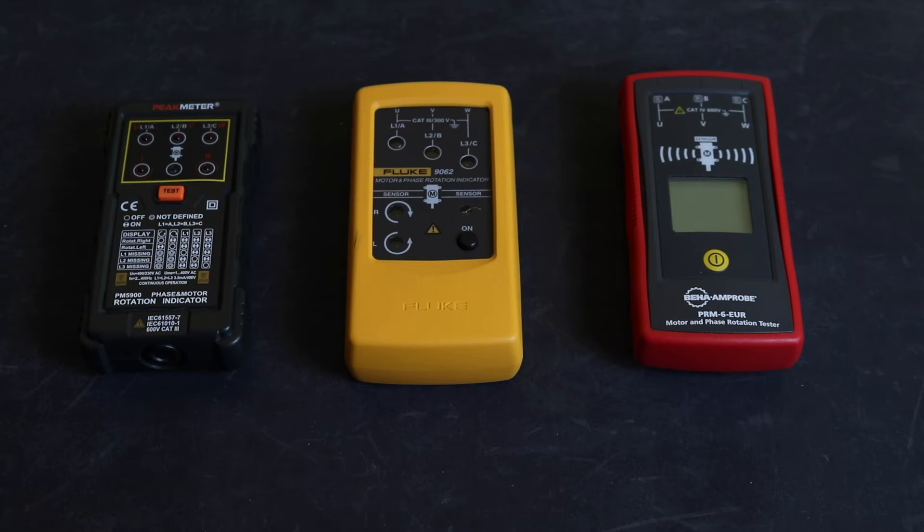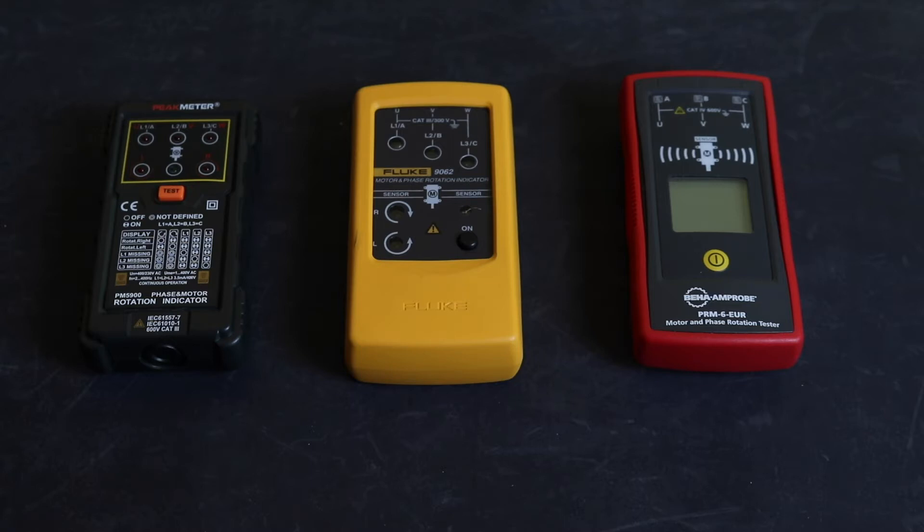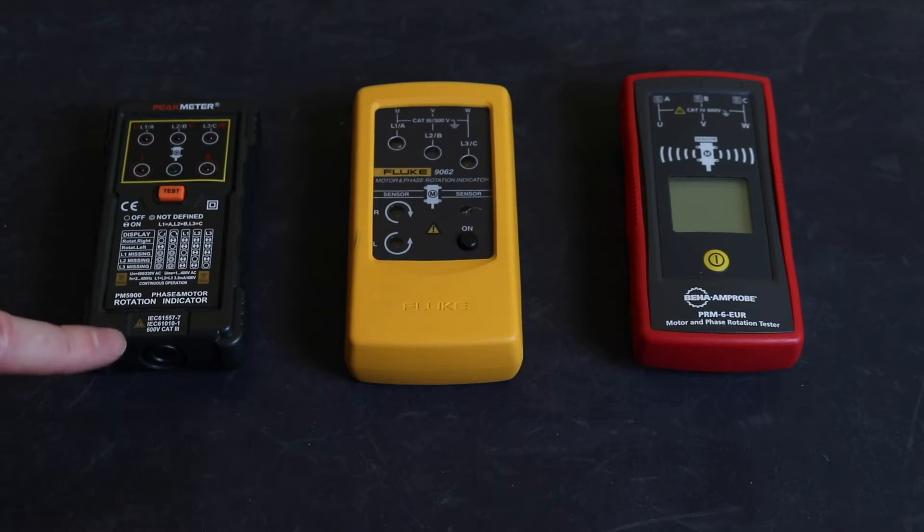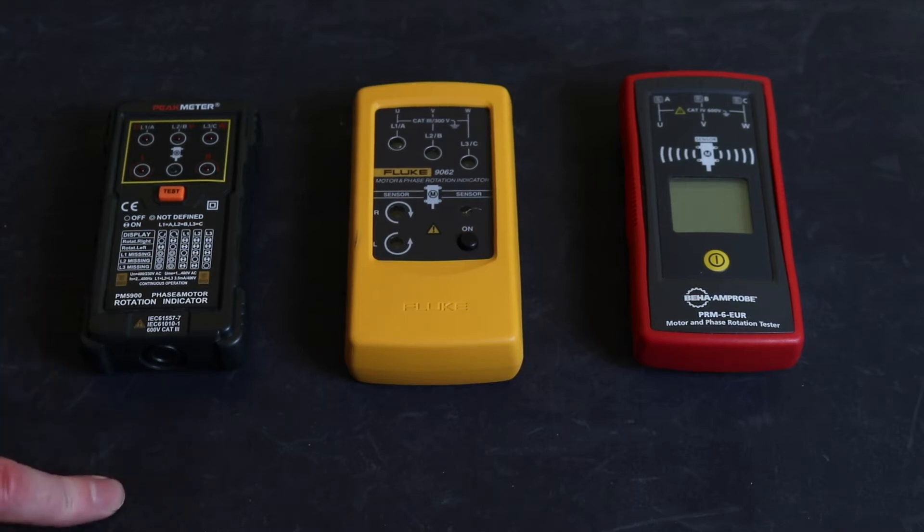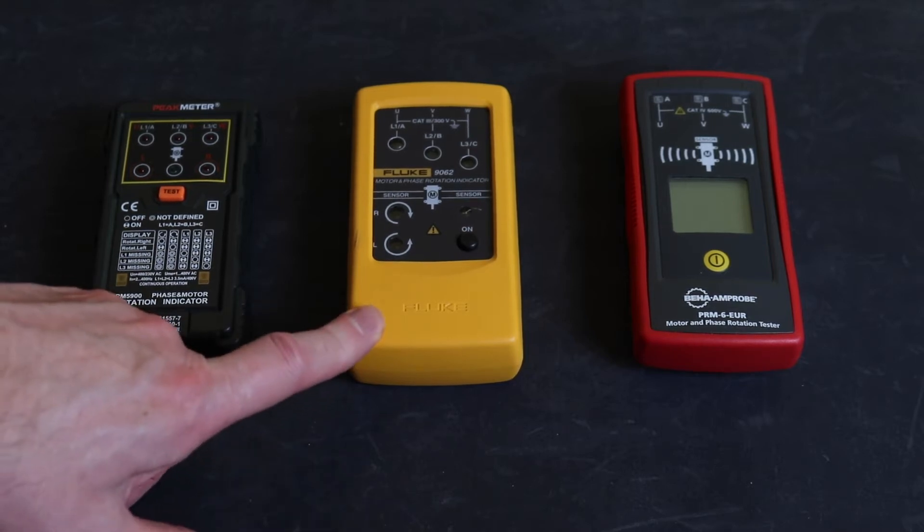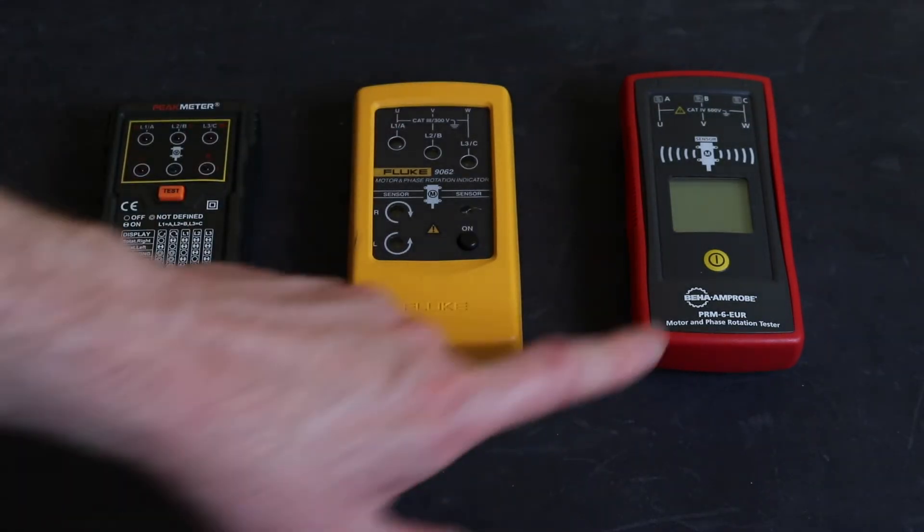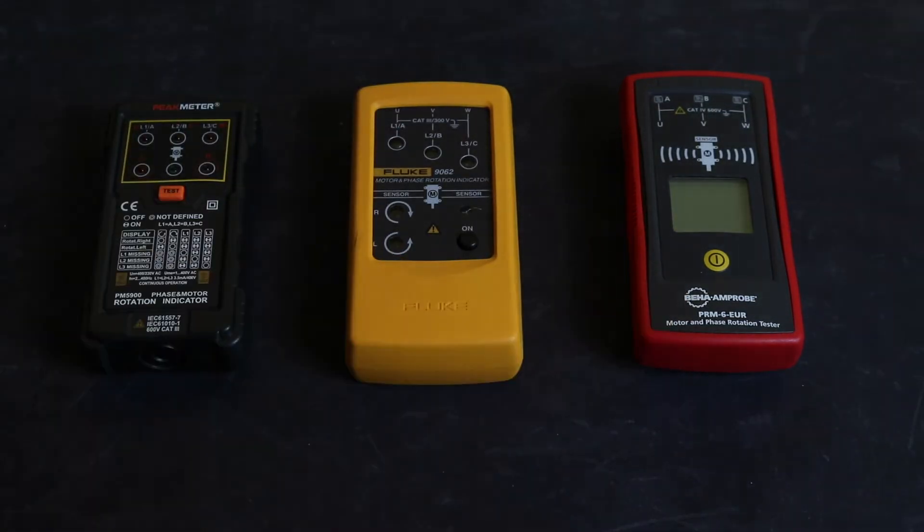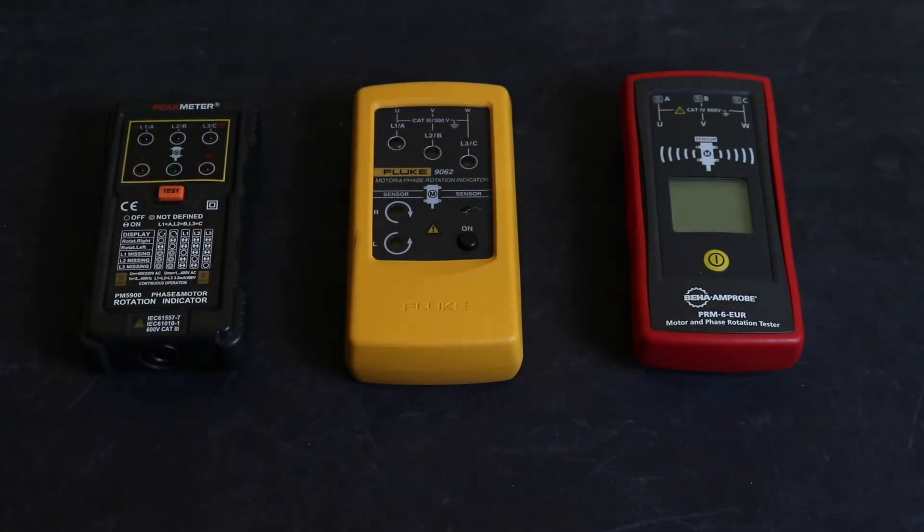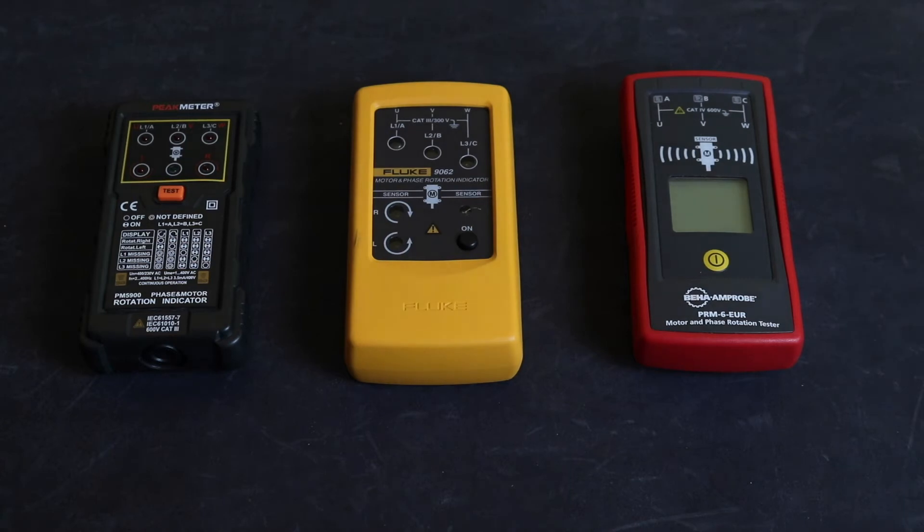Welcome back to the channel. In this video, I want to continue a review of these three phase rotation meters. I'm going to dismantle them and take a look inside. Primarily, I'm interested in the input protection these instruments specify. This one's CAT 3 600 volts, as is the Fluke, CAT 3 300 volts, but this is CAT 4 600 volts for the Beha-Amprobe.